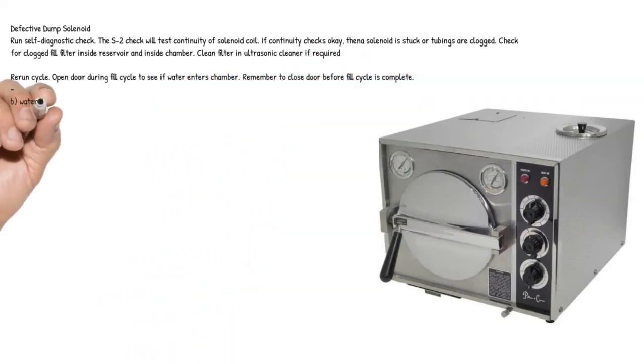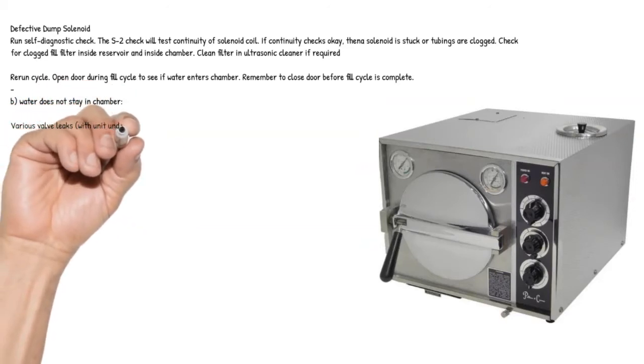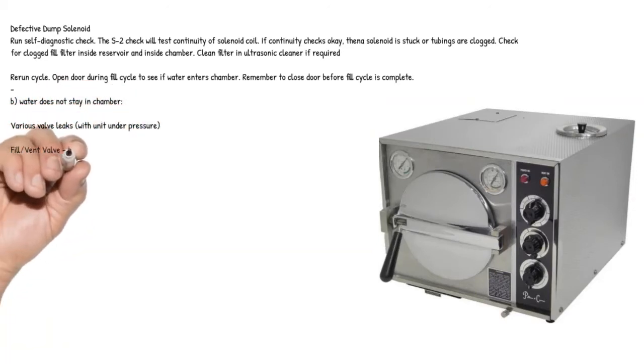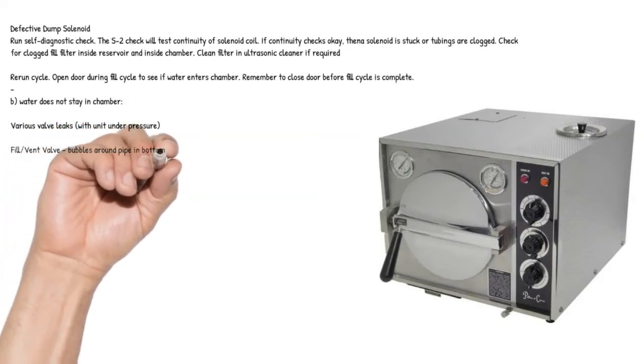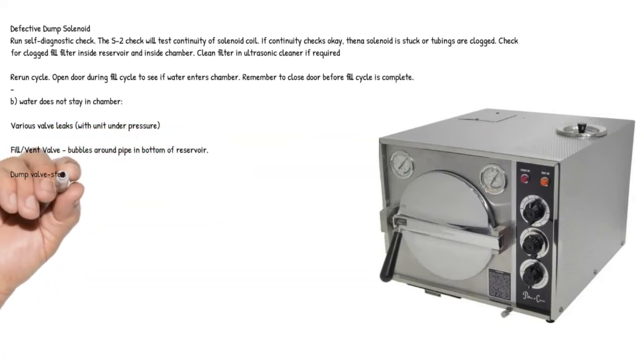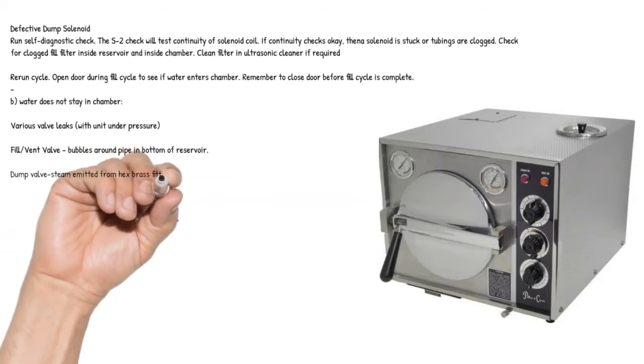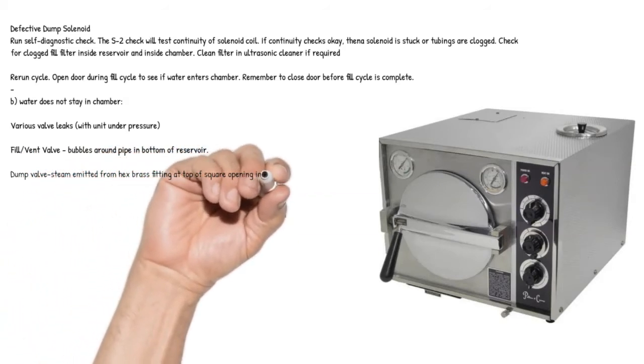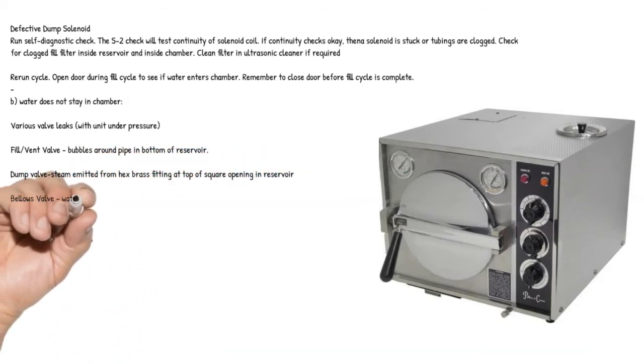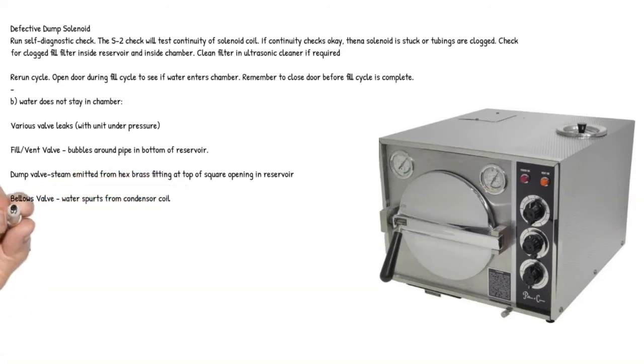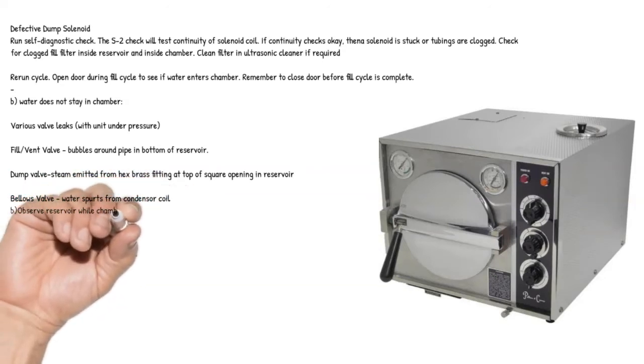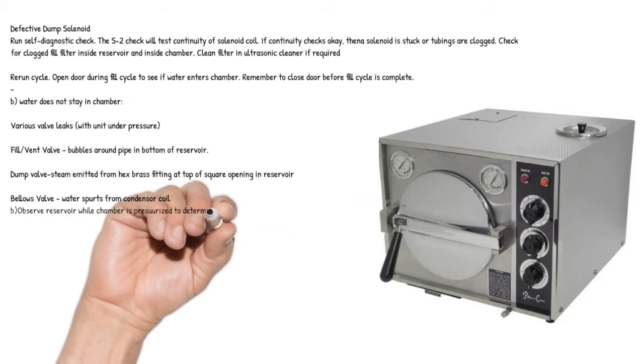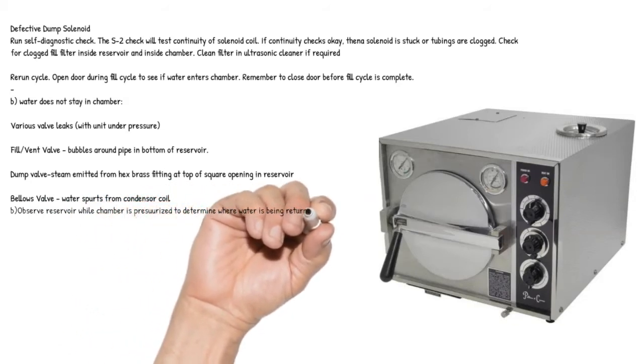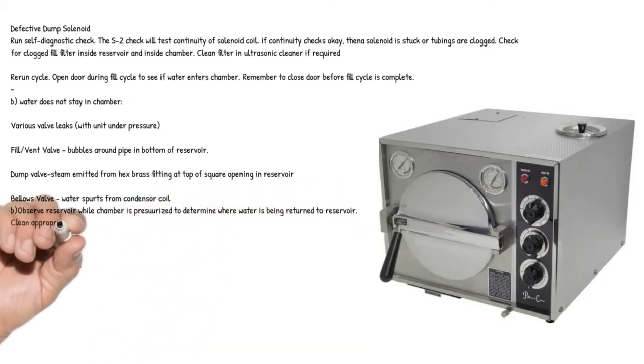B. Water does not stay in chamber. Various valve leaks, with unit under pressure. Fill/vent valve, bubbles around pipe in bottom of reservoir. Dump valve, steam emitted from hex brass fitting at top of square opening in reservoir. Bellows valve, water spurts from condenser coil. B. Observe reservoir while chamber is pressurized to determine where water is being returned to reservoir. Clean appropriate valve seat or replace appropriate valve.